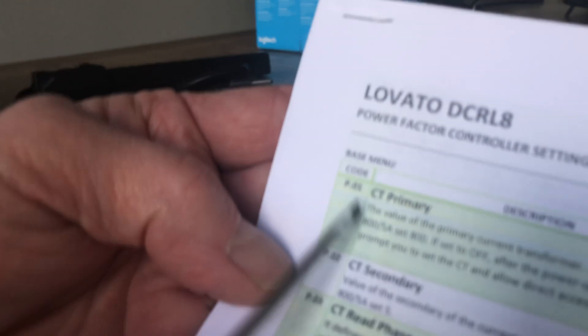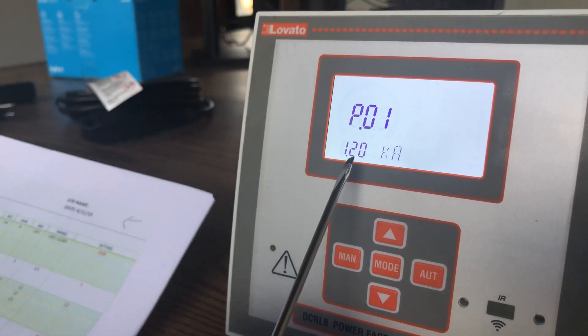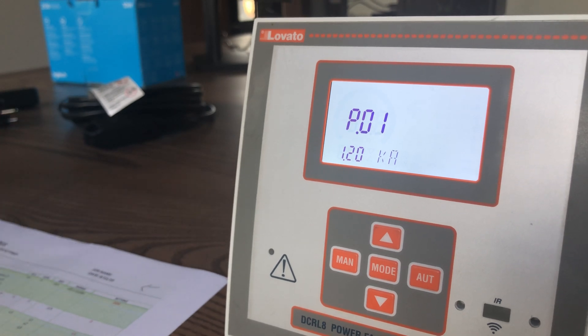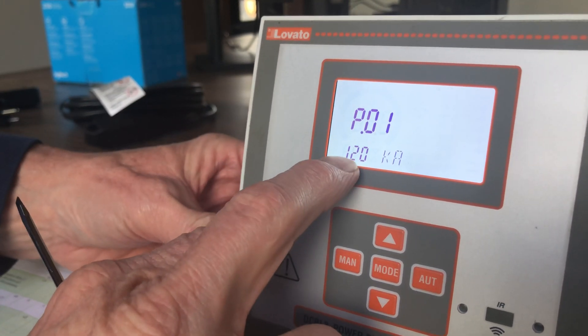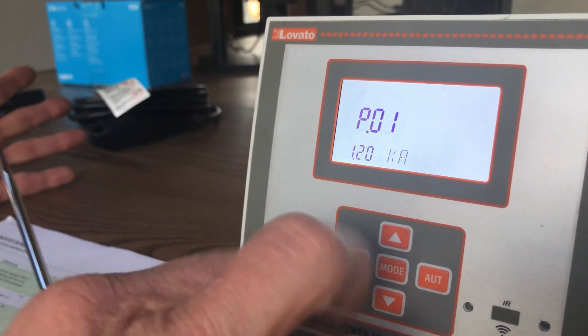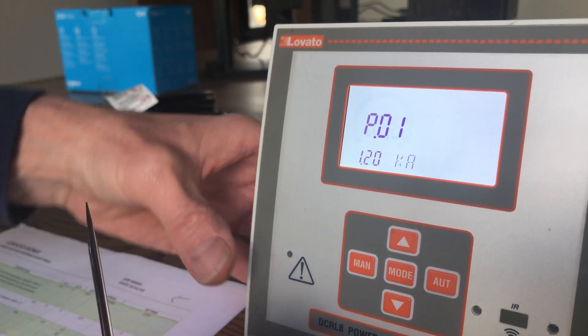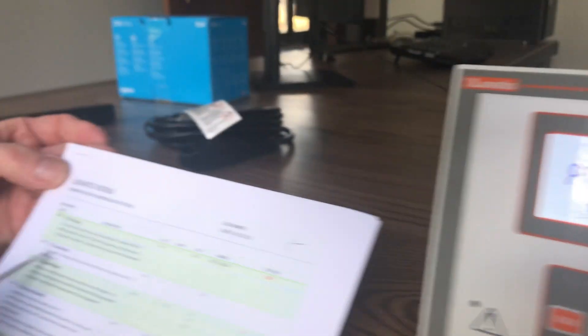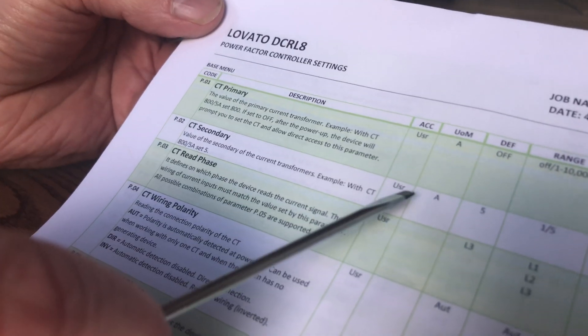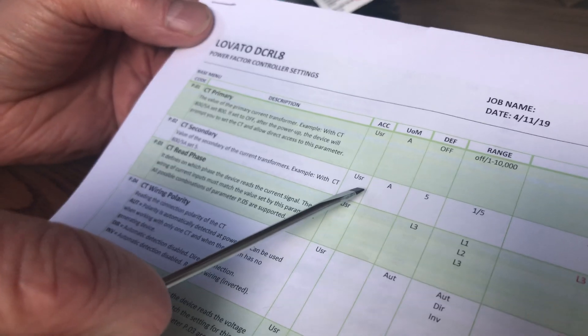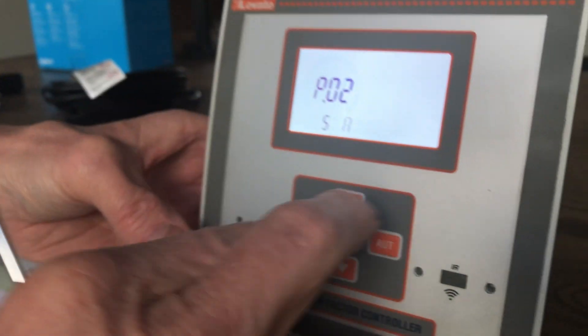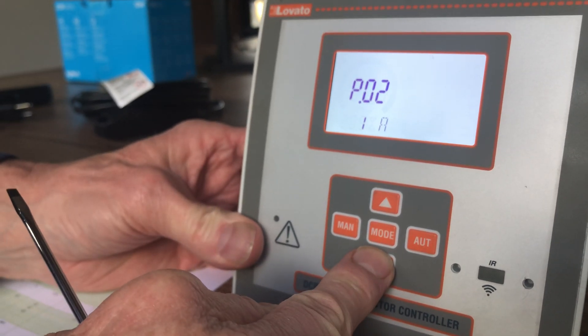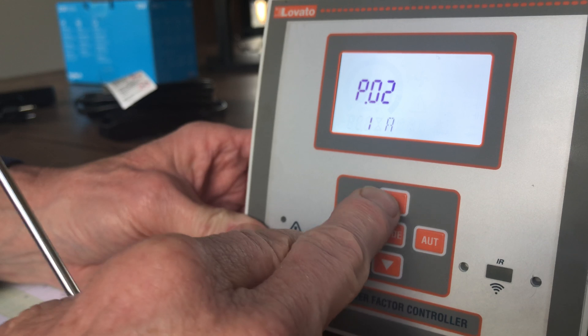The first parameter is P01, which is P01 on your settings sheet, and it says CT primary — that's the primary current rating of your CT, which is located on the bus you're trying to correct. Right now it's set for 1.20 kA, which is 1,200 amps as the primary setting. Hit AUTO again and it goes to P02, which gives you the secondary value — it's 5 — so 1200-to-5 is the CT ratio we have set. If you wanted to change that, you would use the arrow keys.